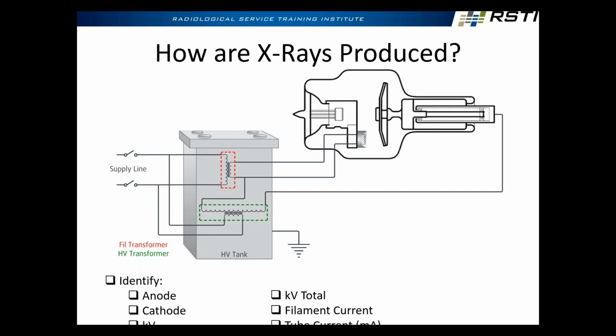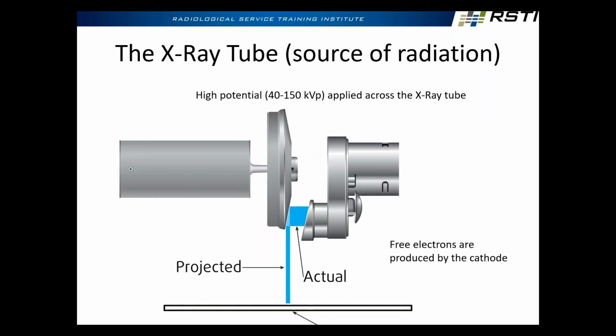All right. In reality, we're going to rectify that, so we'll have full wave rectified output, but even that's not good enough for what we want. We want to get as close as possible to pure DC across that tube to reduce the amount of ripple that we see. All right. So that source, where those electrons are striking, this is what's known as the focal spot.